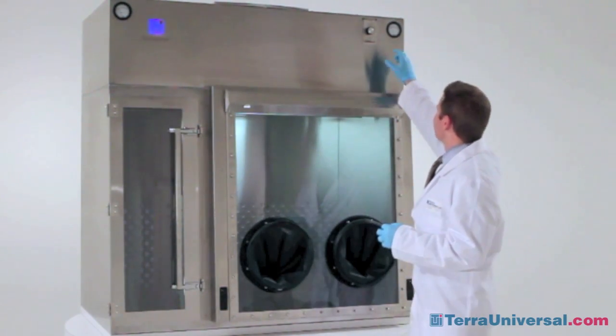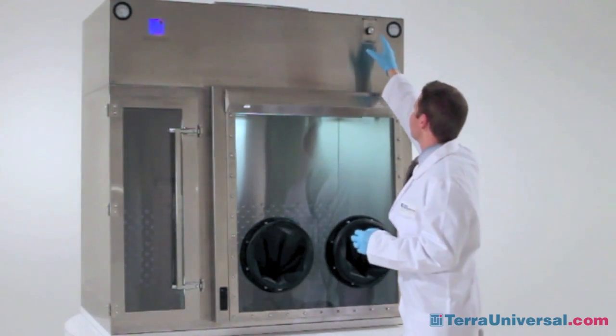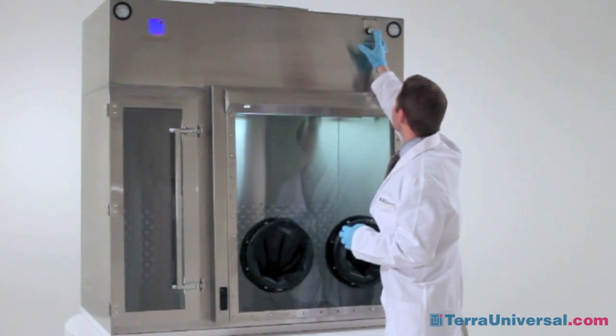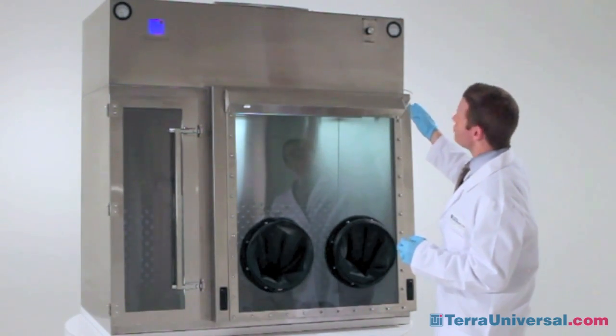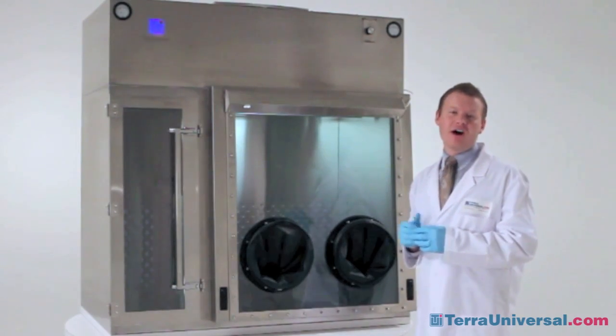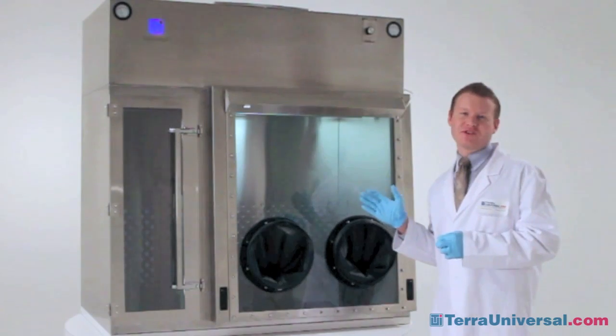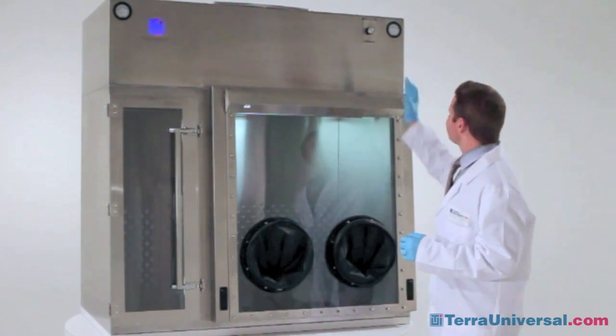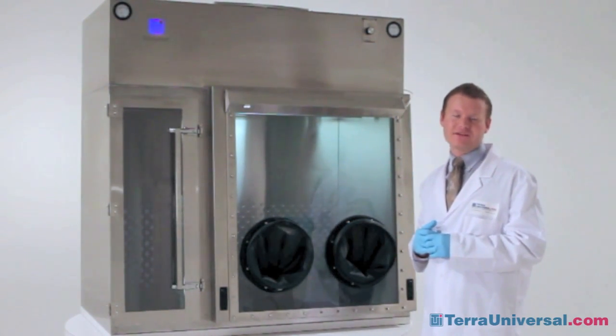As you can see here, we have a smaller pressure differential than the needed 0.1 inches water gauge, but the fans are nearly off. As I turn the fans on to a medium position, you'll see that the 0.2 and 0.1 inch water gauge requirements are attained. If you do experience some filter backup after years of use, you can simply turn the fan to an even higher position, as you have some leeway with maintaining those conditions.